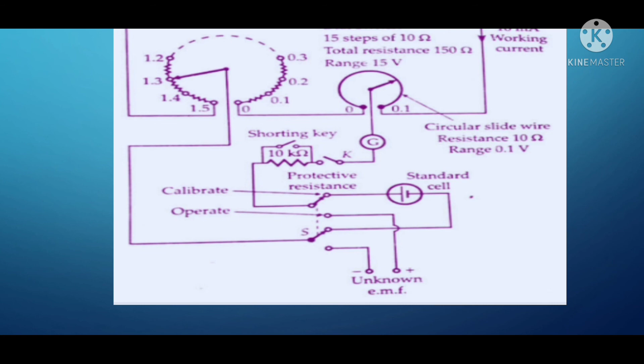While measuring, we need to check its accuracy once again. For checking accuracy, the double pole double throw switch is placed at the calibrate position once again and checked for the position of the two dial switches.